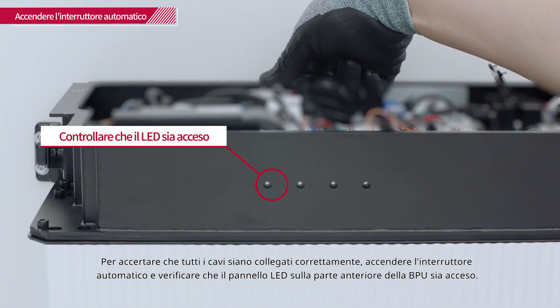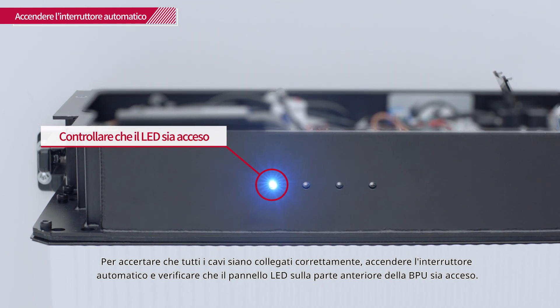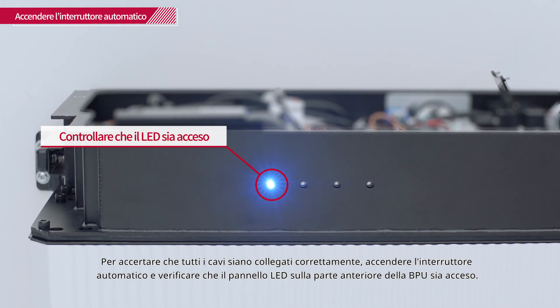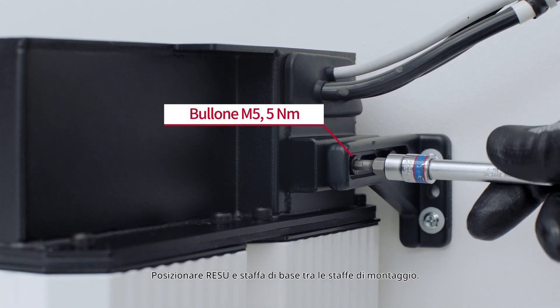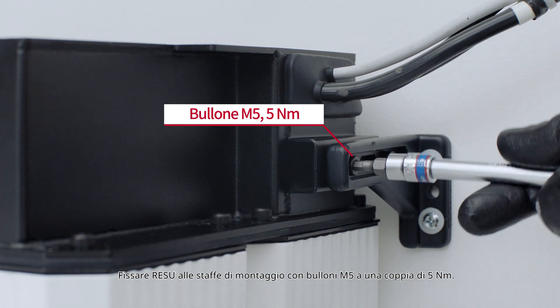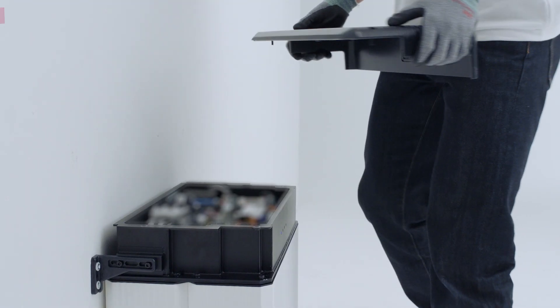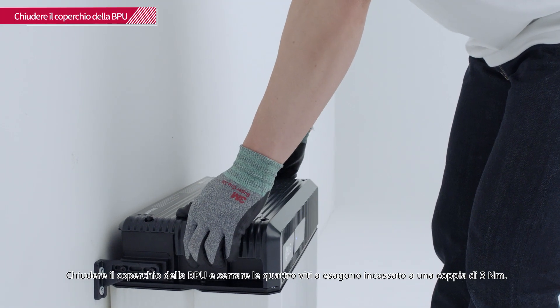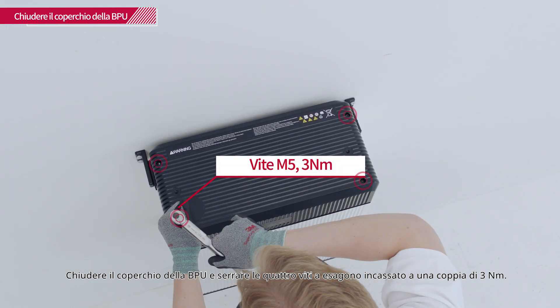To ensure that all the cables are properly connected, turn on the circuit breaker and check that the LED panel on the front of the BPU is on. Place the RESU between the mounting brackets and fix it with M5 bolts with a torque of 5 Nm. Close the BPU cover and tighten the 4 hex socket screws with a torque of 3 Nm.